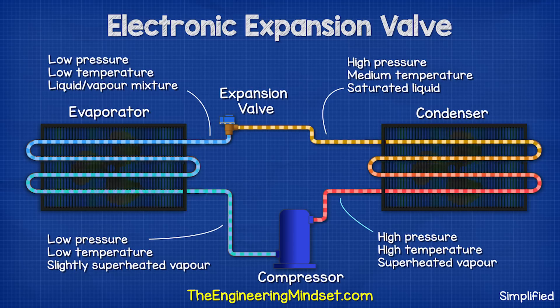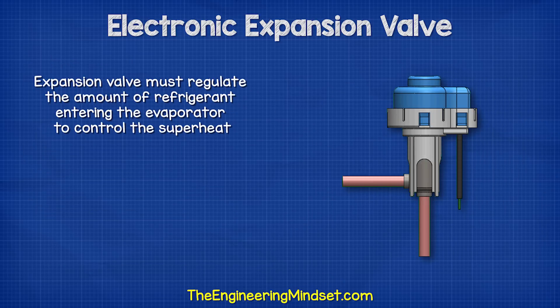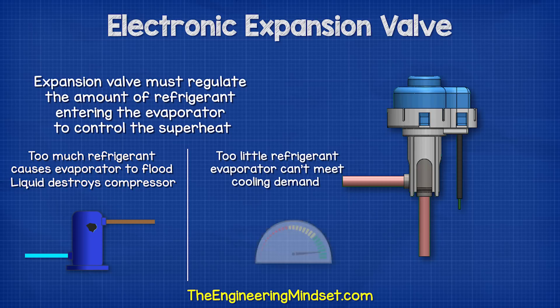The refrigerant therefore exits as a high pressure, medium temperature saturated liquid and this heads to the expansion valve. The expansion valve needs to regulate the amount of refrigerant entering the evaporator to control the superheat. If it allows too much refrigerant to flow it can flood the evaporator, so the refrigerant doesn't evaporate, a liquid reaches the compressor and possibly destroys it. But if it lets in too little refrigerant the system won't provide enough cooling and so it operates inefficiently.